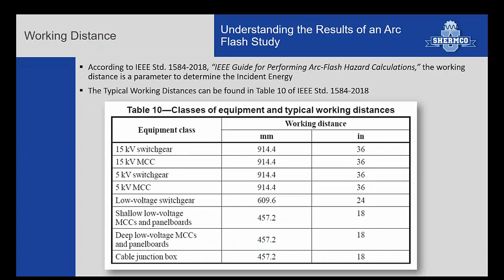And those come from IEEE 1584. They give working distances that are typical that most engineers will use for the study. There's all types of gear out there. This is a good start, and this is what most engineering firms use. If your gear's a little different or unique, maybe these aren't the right distances, or maybe if you're doing a task that allows you to be further away, then maybe the incident energy is different than what the sticker shows.